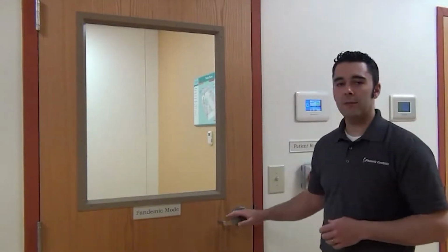What I have behind me is a patient room with a special feature that we call Pandemic Ready Mode. Now, when we started developing healthcare products for the industry, we wanted to make products that were a lot easier for the users to program and get started up, because when you're starting a job, if you can reduce the startup time and the startup cost, you're going to save the customer money in the long run. So this pandemic ready mode uses the tracking pair functionality that the Phoenix Controls valve has, and in this particular application, we're actually using a supply valve, a general exhaust valve, and a return valve.